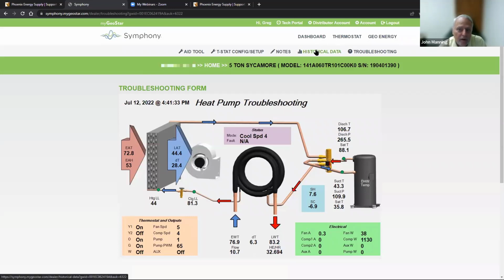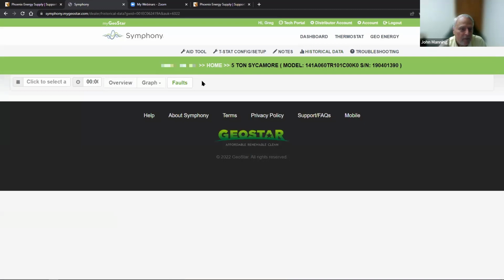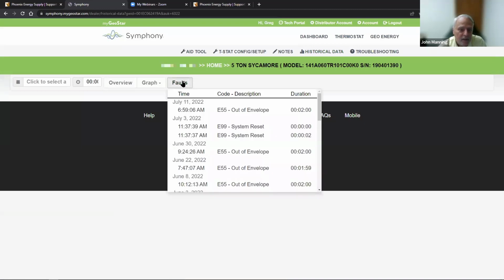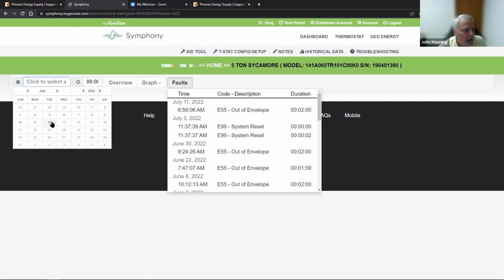Another favorite one is to go to historical data, and we can look up faults. And this one on July 11th gave us an out of envelope fault. That one does occur quite often in the early part of the cooling season when technically the compressor is not seeing conditions within a defined envelope. It's nothing to be alarmed about. It won't go into lockout. But let's just take a look at today's data.